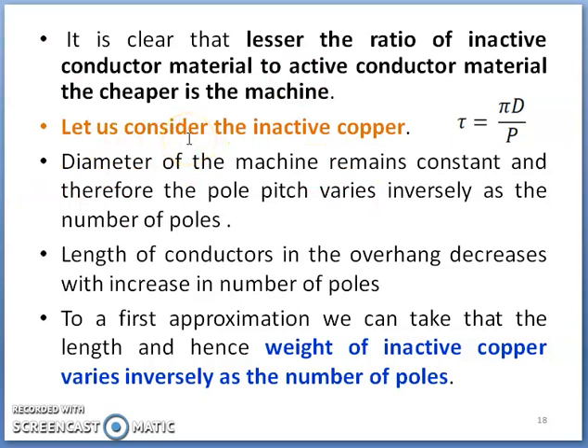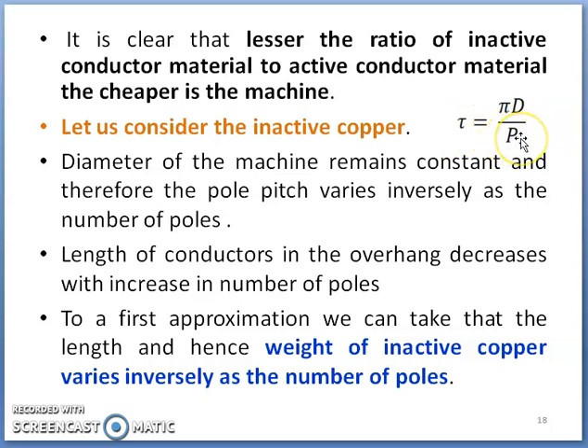Considering the effect of inactive copper: since the diameter of the machine remains constant, the pole pitch varies inversely as the number of poles, as per the equation τ = πD/P. If the diameter of the machine is kept constant, then pole pitch depends upon number of poles and these are inversely related. The length of conductor in the overhang decreases with increase in number of poles. Because of this, the weight of inactive copper varies inversely as the number of poles — as the length of inactive copper decreases due to increase in number of poles, the weight of inactive copper will be less for a large number of poles.